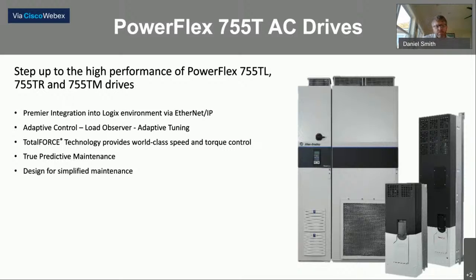It's also very compact in design. When replacing an inverter or a converter, you don't have to unwire the motor cables to replace those components. They slide right out, and all your terminations stay in place. Our 755 TR drive is a regenerative drive. Those drives are used a lot in winding applications. There's a fair amount of them now on paper machines, where they're sharing load and doing load sharing.